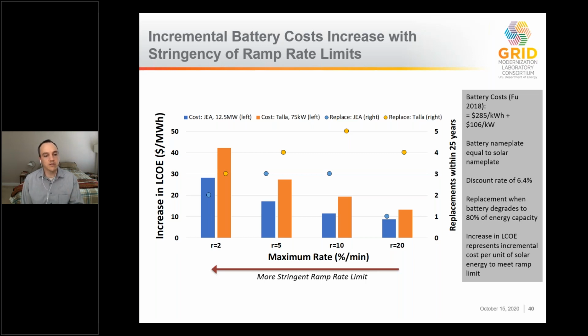One other interesting finding from this chart is that the costs were higher when we looked at this for just this small 75 kilowatt PV system using PV data from the city of Tallahassee. That's what's shown in the orange bars. And that's relative to the blue bars, which are a 12.5 megawatt PV system that was located in Jacksonville. And presumably the lower cost that we see here for that larger plant happens because there was less need for the batteries to be rapidly cycled to provide that smoothing, because even within that single power plant, there was already some smoothing that happens. There's already some effective aggregation that smooths out the output of those cloud-induced fluctuations. And so the resulting changes in output that had to be provided by the storage asset were less for that larger footprint plant.